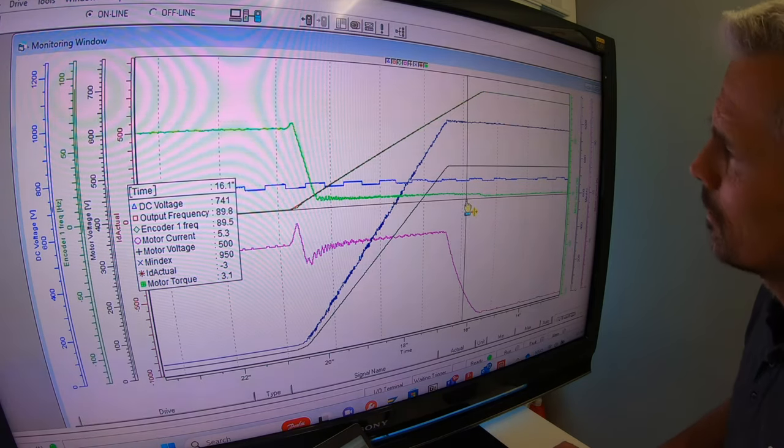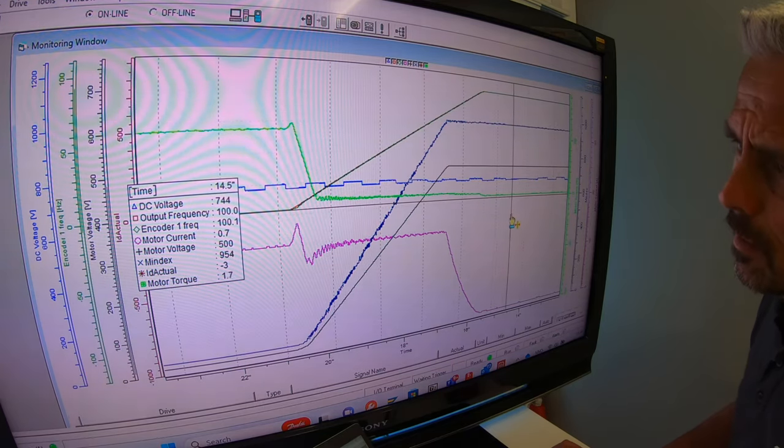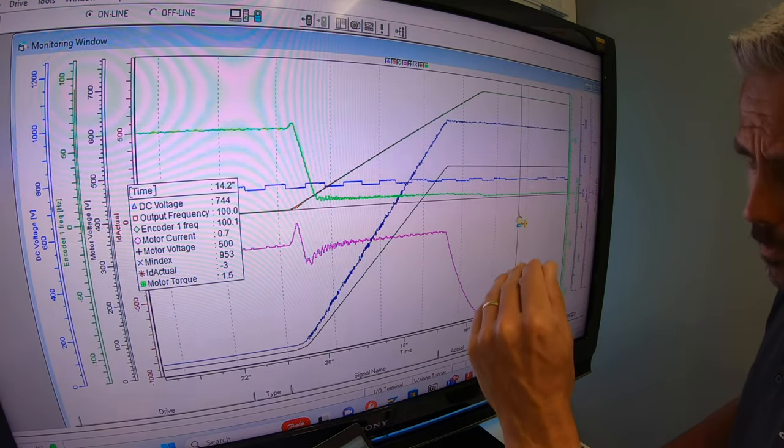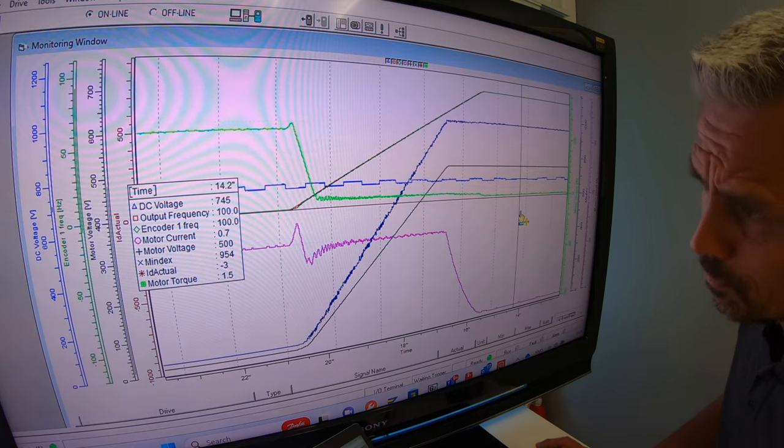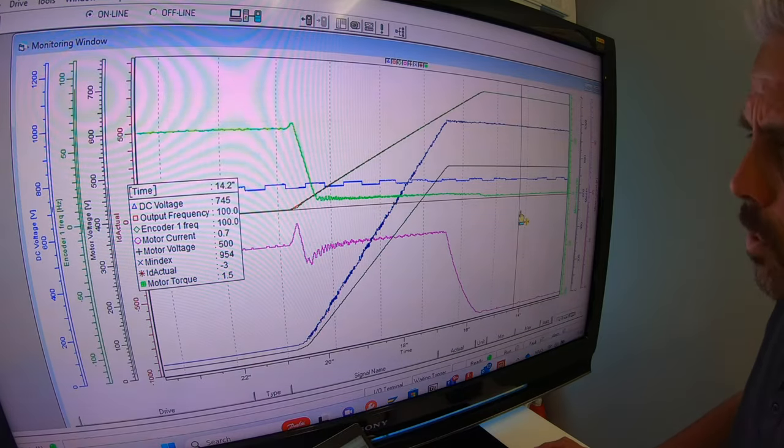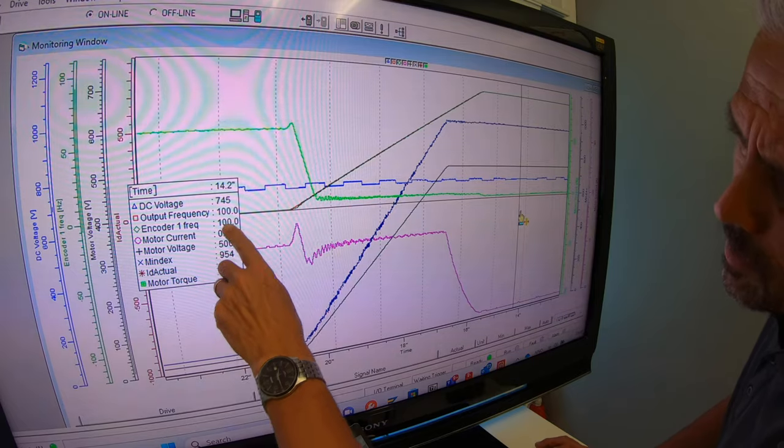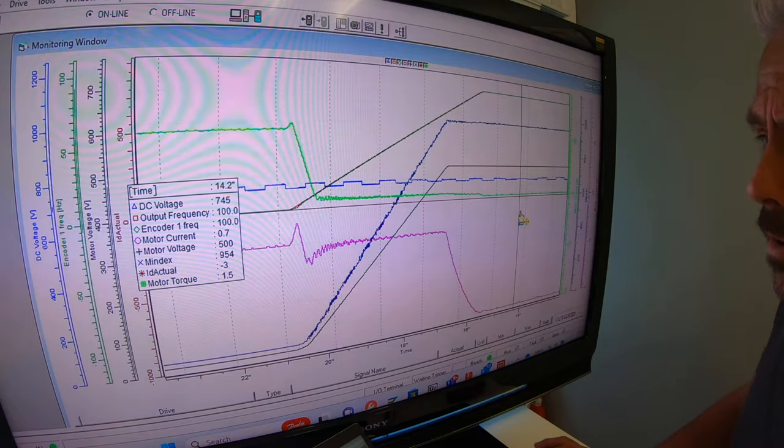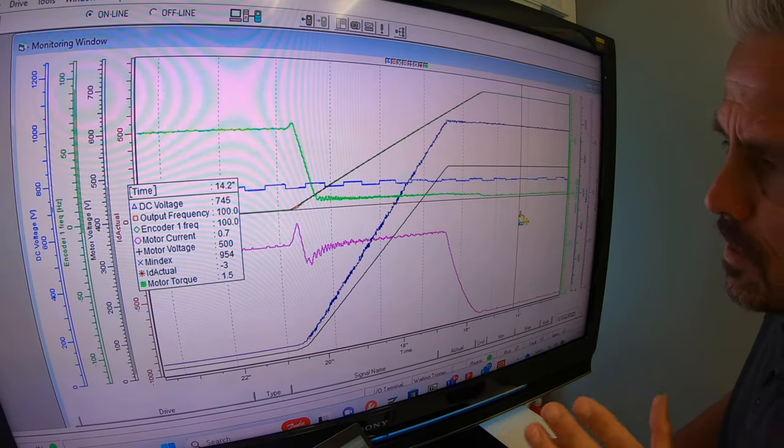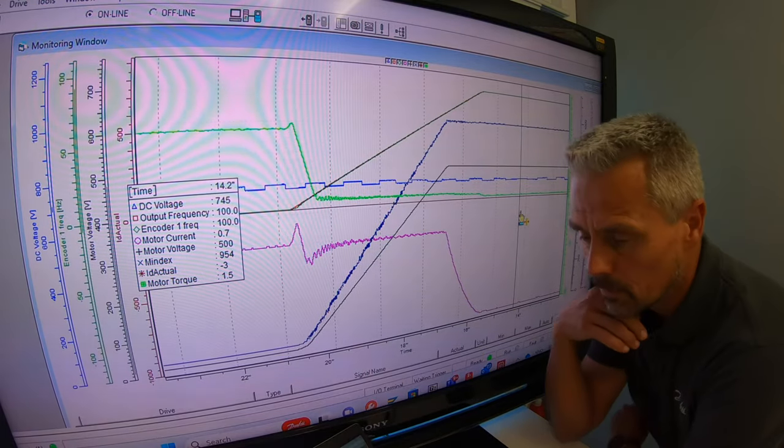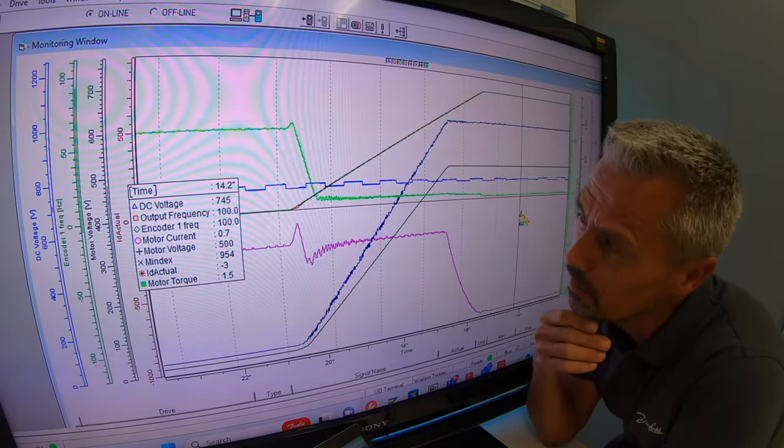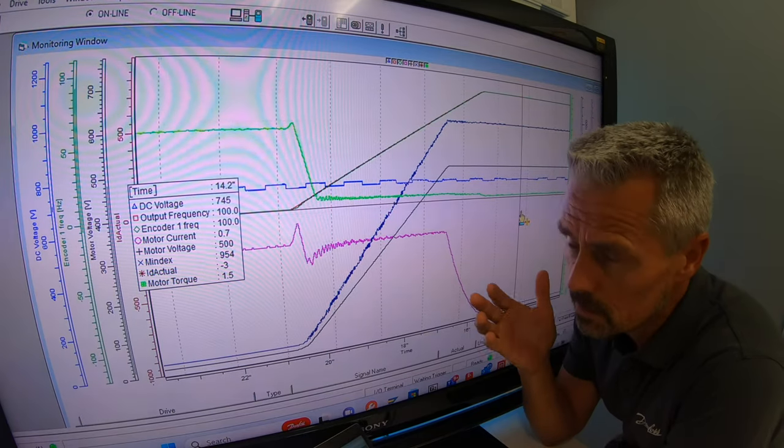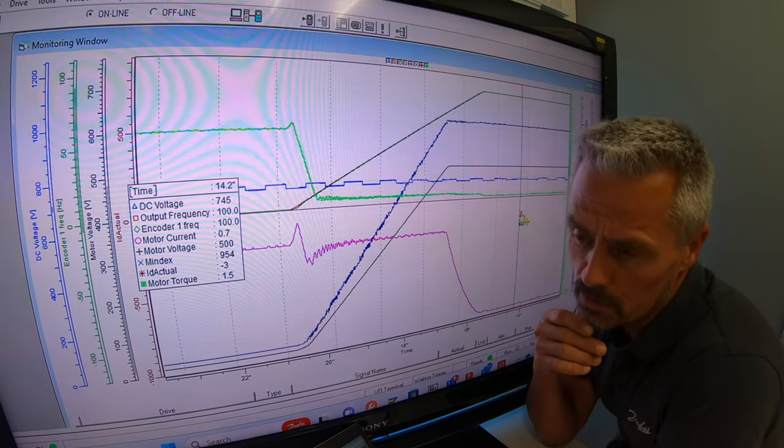When we increase the speed of the motor, then the UF curve will hit almost nominal and we sit here at 100 hertz, which is nominal. The current is almost nothing and the motor voltage sits constant at 500 volt. Modulation index is 95 percent when our DC voltage is 745 volts. It means that we have enough DC voltage to produce these 500 volts. So this is a good one. This is a setting where this motor actually could do a good job in a practical installation, thruster or anything, in an open loop setting. So this is actually the complete tuning of our open loop system. And you find this in rim thrusters, thrusters without encoders, and so on. You can set it up for sensorless closed loop and IF control.